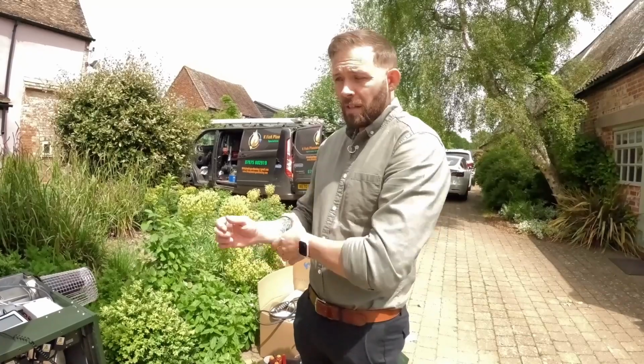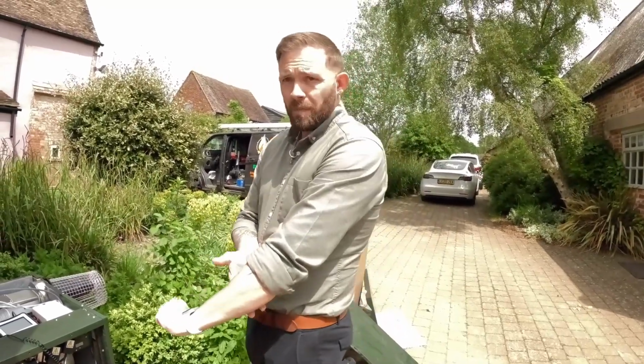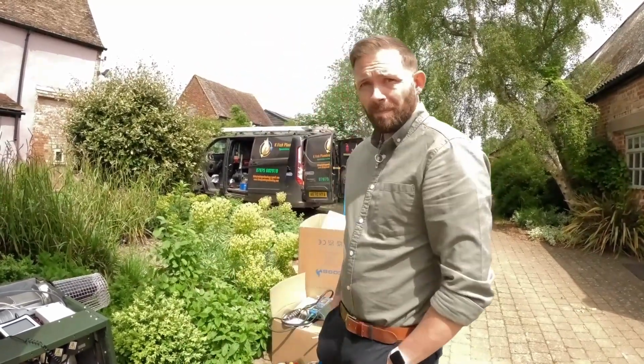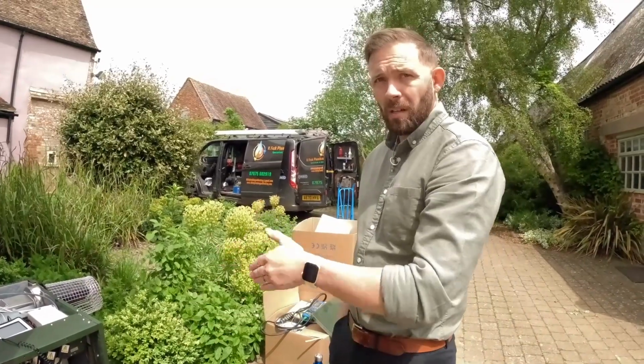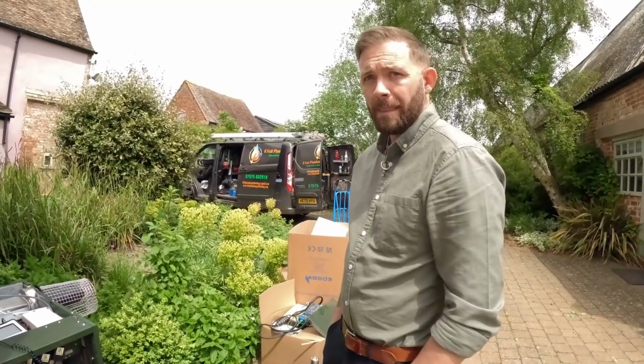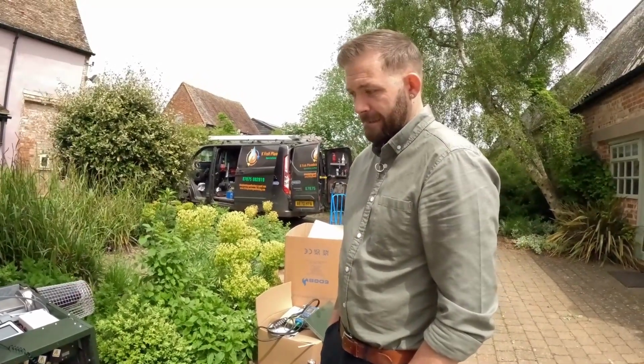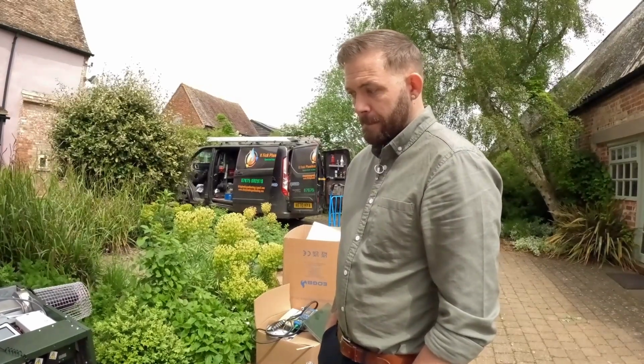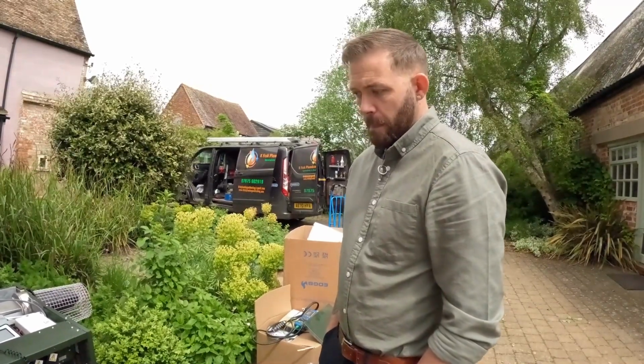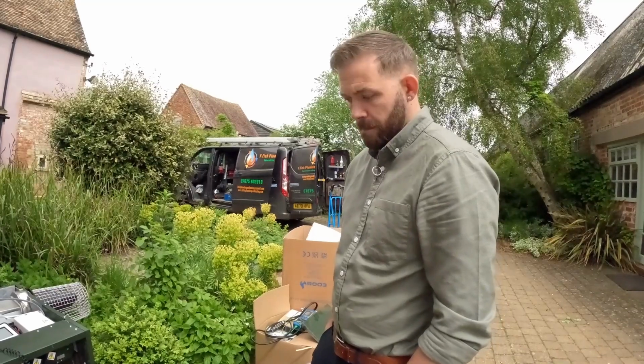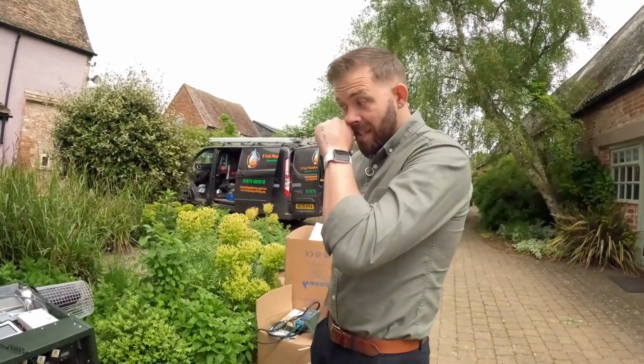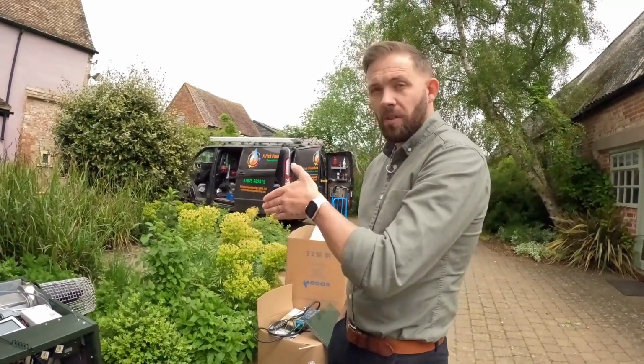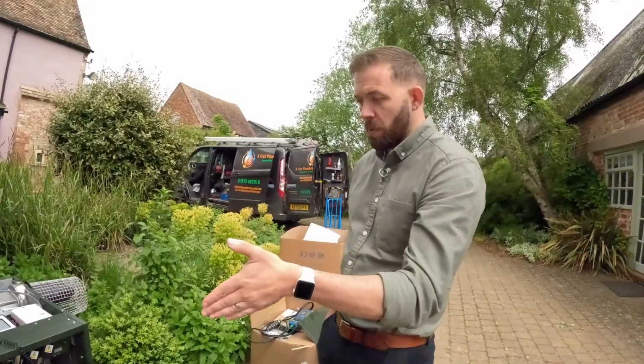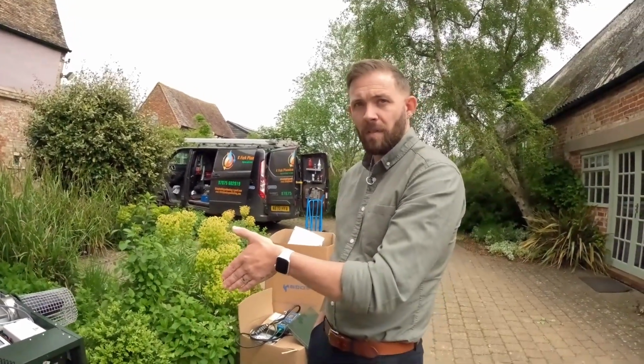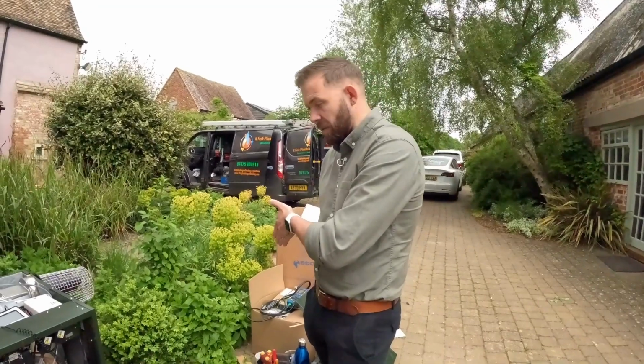And the boilers are rated from 6 kilowatts to 32. Yeah, they come out of the box at 28. Okay, so it'll be a 9 to 28 kilowatt. Yeah, so that's really good for me, because you've got one boiler in a box. If you put a 23 or a 24 kilowatt in and someone puts a big extension on the side of their house, it's literally just an oil nozzle change, isn't it? It is, yes. And obviously we've got a 23, 28 and a 32 of the 3 ranges. Yeah. So a 0.45 nozzle in the first one, 0.55 in the second one, 0.65 in the third.